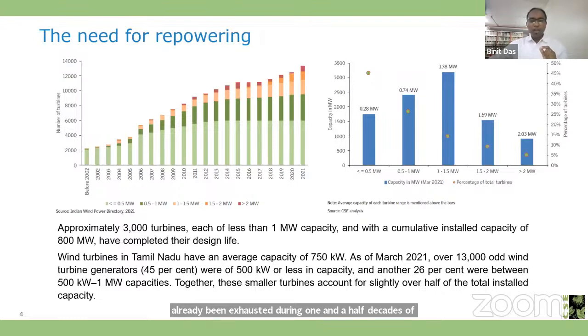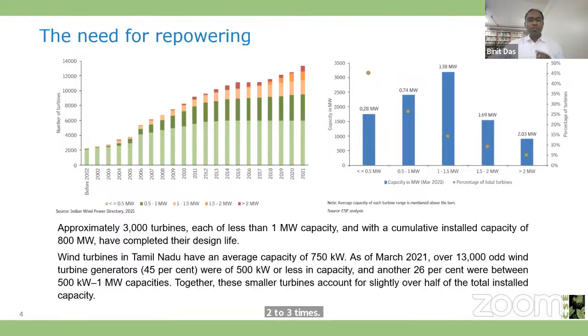During one and a half decades of the sector's development since the 1990s, the plant load factors of old wind turbines populating these sites are very low, at 10 to 15%, compared to more than 30% achievable by modern wind turbines. If we repower these old turbines with class 1 turbines, this capacity can be increased by 2 to 3 times. We can increase the plant loading factors and the annual energy production as well.